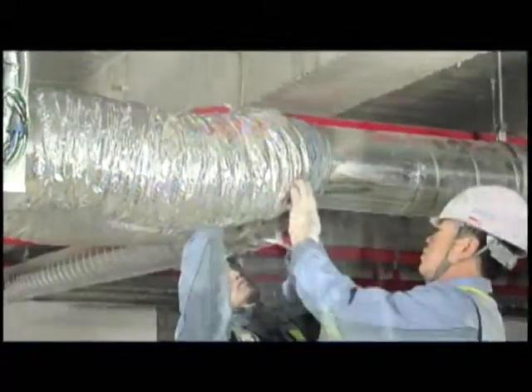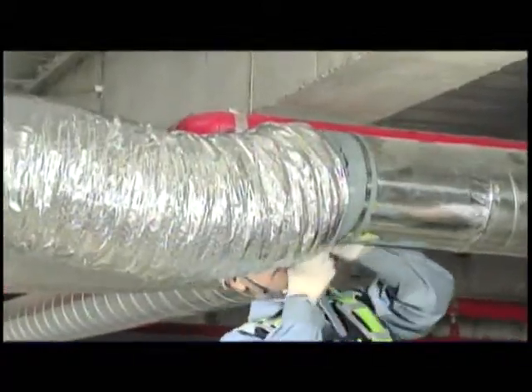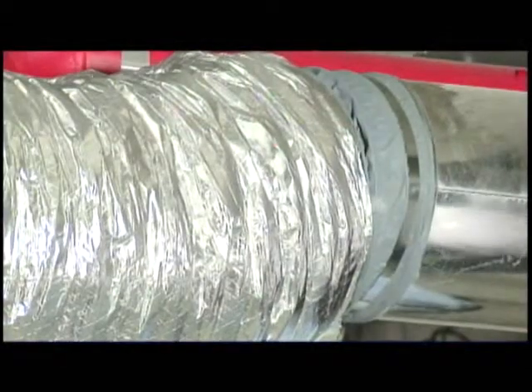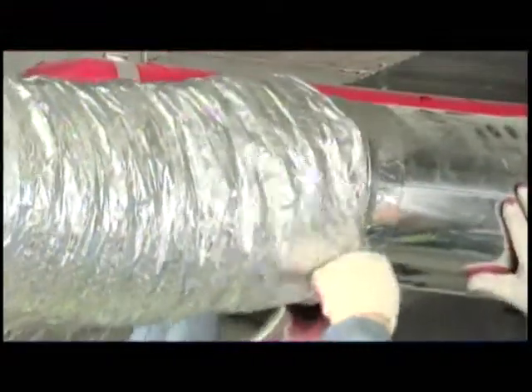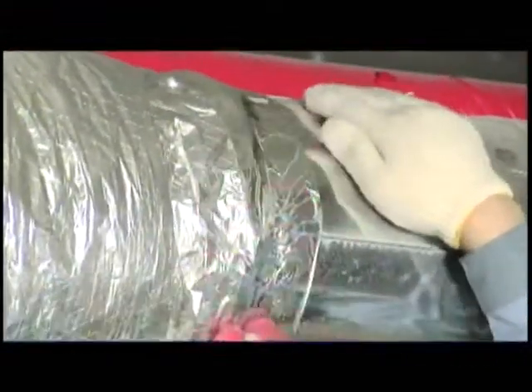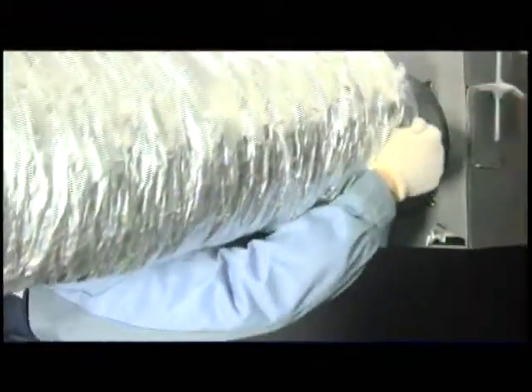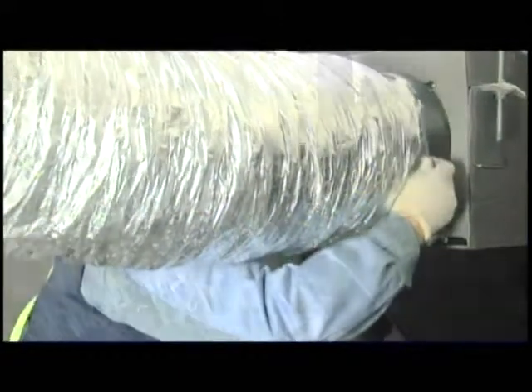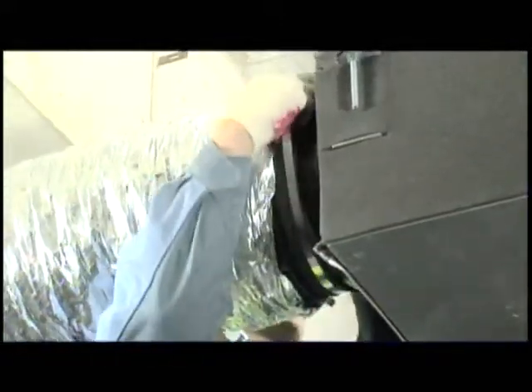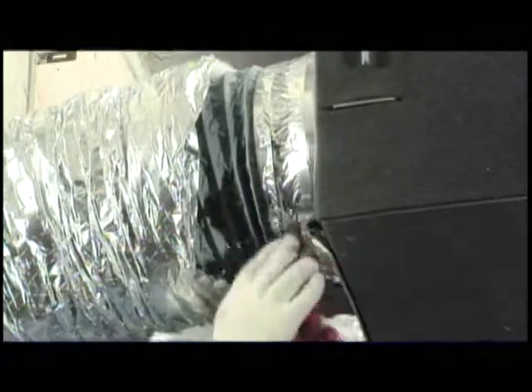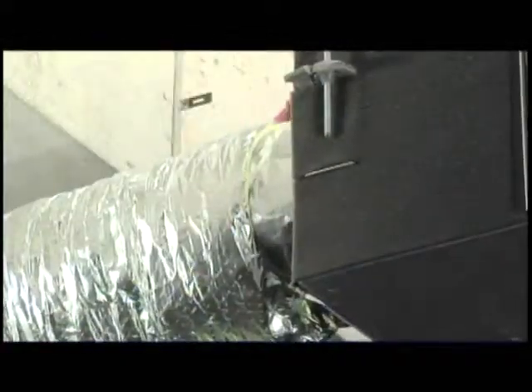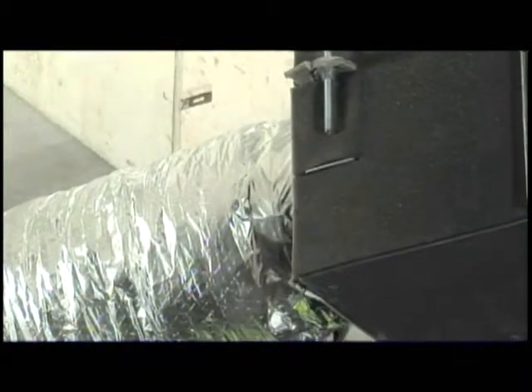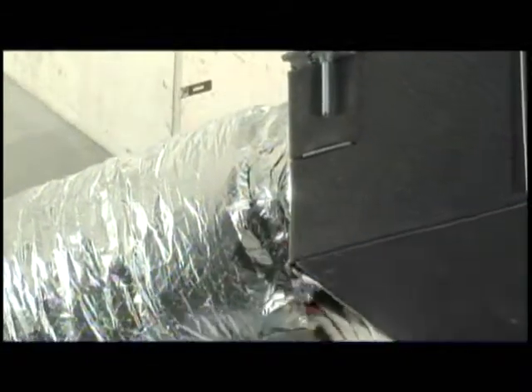To connect the equipment and the hood, fix the ventilation hole and the flexible duct with a clamp and finish it with aluminum tape to prevent air leakage. All the ducts connected to the external hood should be insulated. If the equipment is installed in an external environment, then all the ducts and equipment connected to the indoors should be insulated.